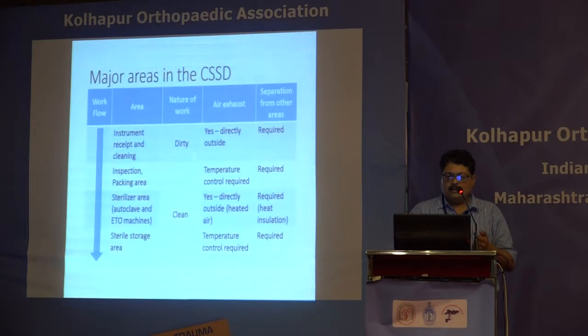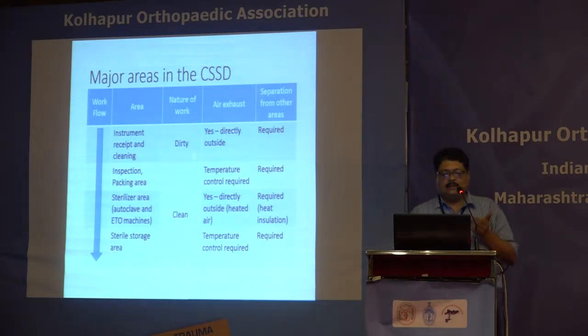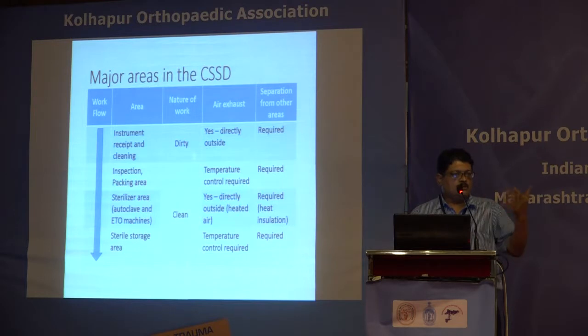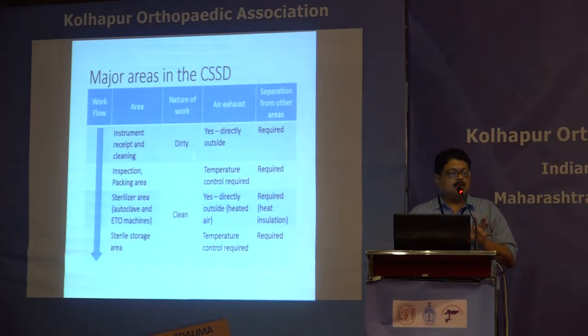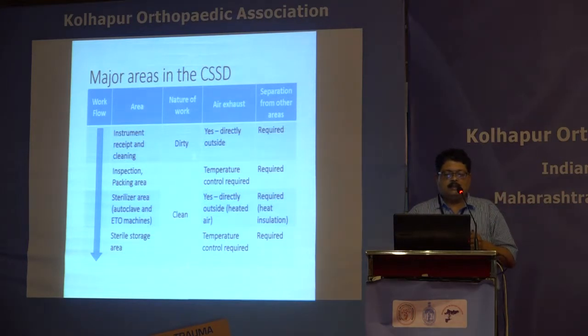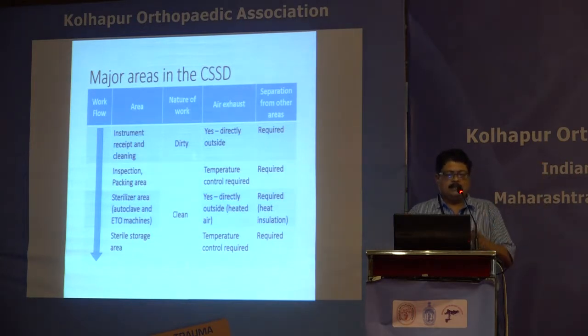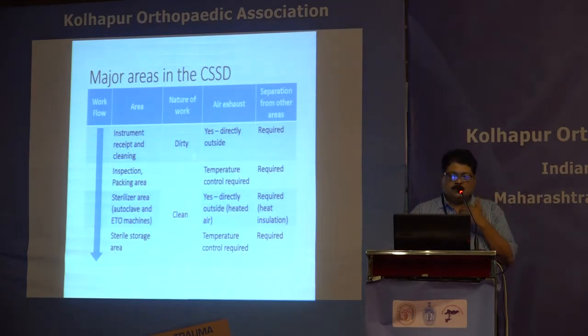These are the major areas in an ideal CSSD if you have the space for all four separate areas. First is the instrument receiving and cleaning area, where dirty work is done — blood and body fluids will come there. The air must be exhausted directly outside; a simple exhaust fan above the basin can be sufficient, and separation from other areas is required. The second area is inspection and packaging: after cleaning and drying, instruments and linen come here, drums and trays get packed, and indicators are added. From this point onwards everything is clean activity.